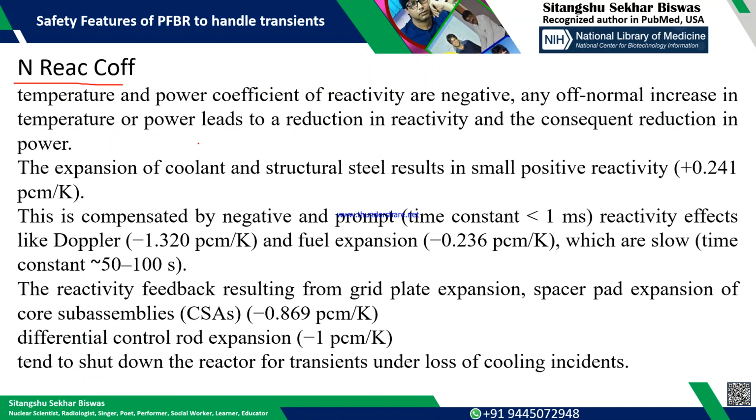Only the expansion of coolant and structural steel results in a small positive reactivity, around 0.241 pcm per Kelvin. When there is an expansion of coolant and the geometry of the reactor, the geometric buckling of the system will change.